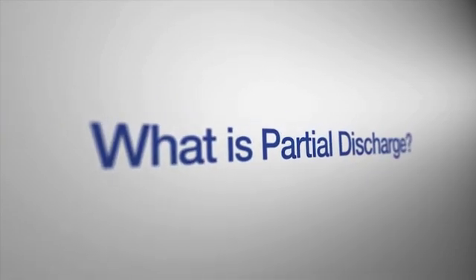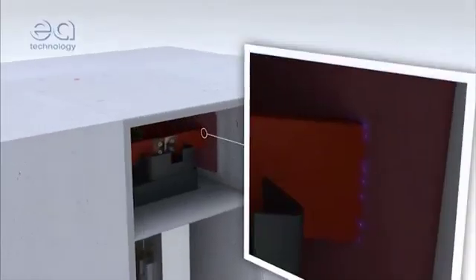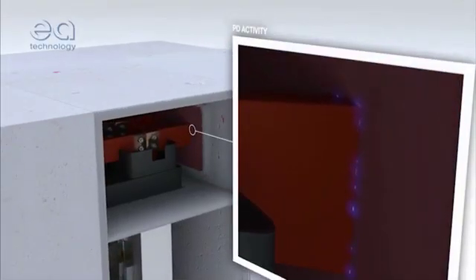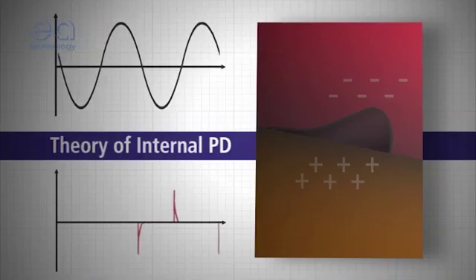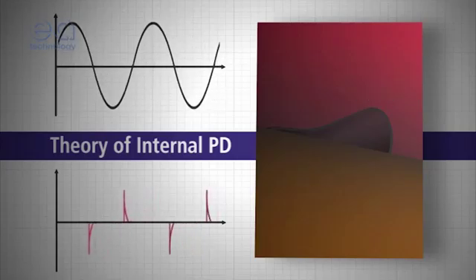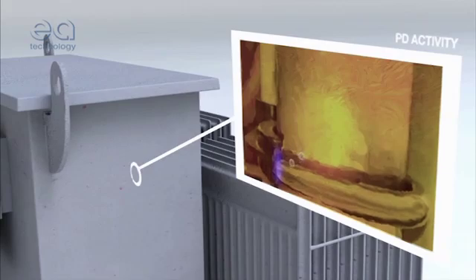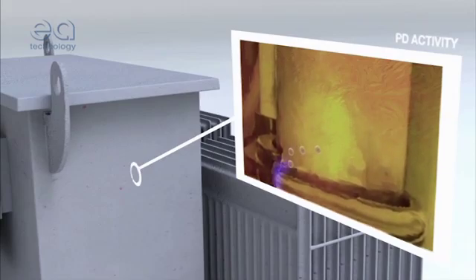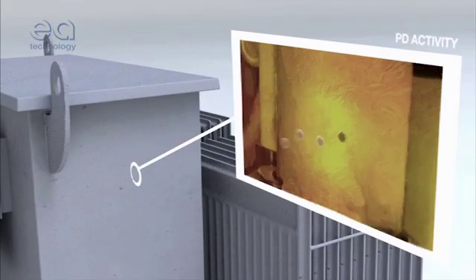A partial discharge is an electrical discharge or spark that bridges a small portion of the insulation between two conducting electrodes. We call this PD activity, and it can occur at any point in the insulation system where the electric field strength is greater than the breakdown strength of the insulating material.